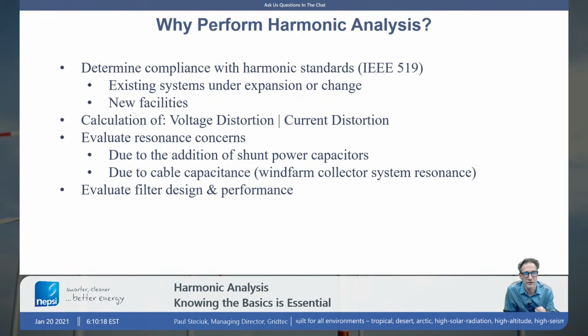You might need to calculate voltage distortion, current distortion. As a rule of thumb, when we do our analysis, our philosophy is to not have greater than 5% voltage distortion within the plant. We're going to operate that plant, and we want to make sure that the power quality is good enough for problem-free operation of your process facility. So voltage distortion is an important parameter, more important than current distortion within the plant, because voltage distortion determines power quality within your plant. It's what all the loads see. They're connected across the bus bars.